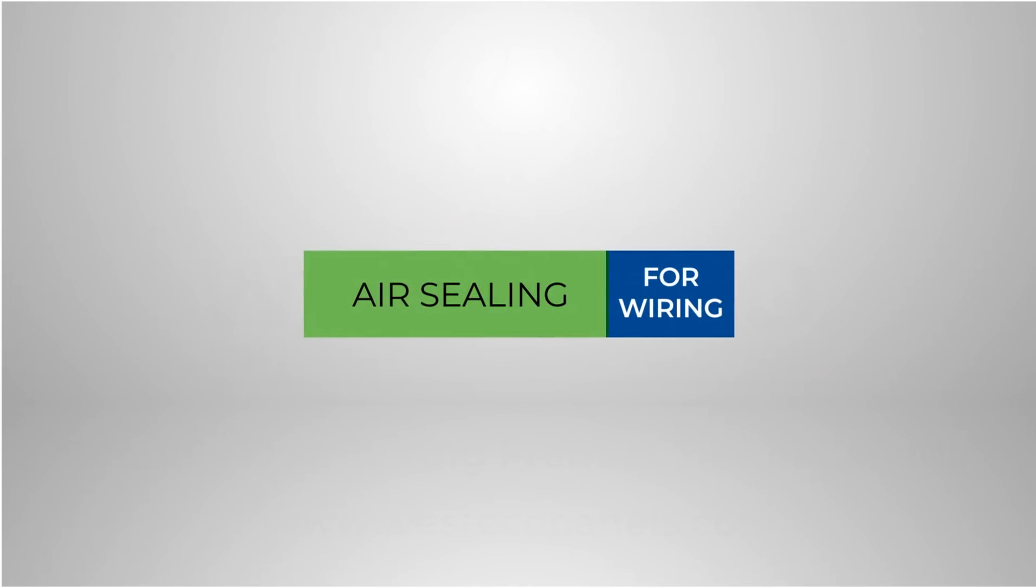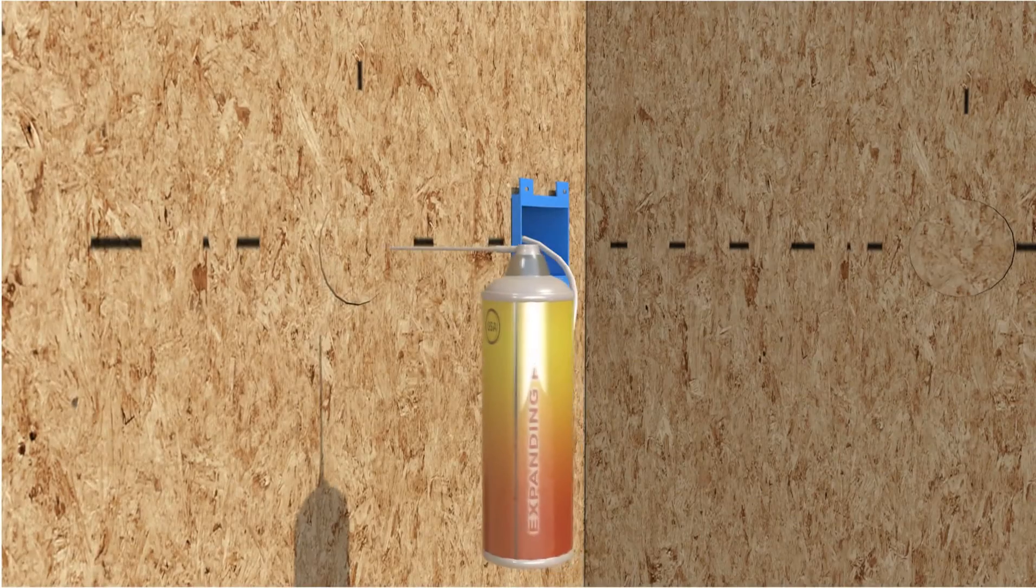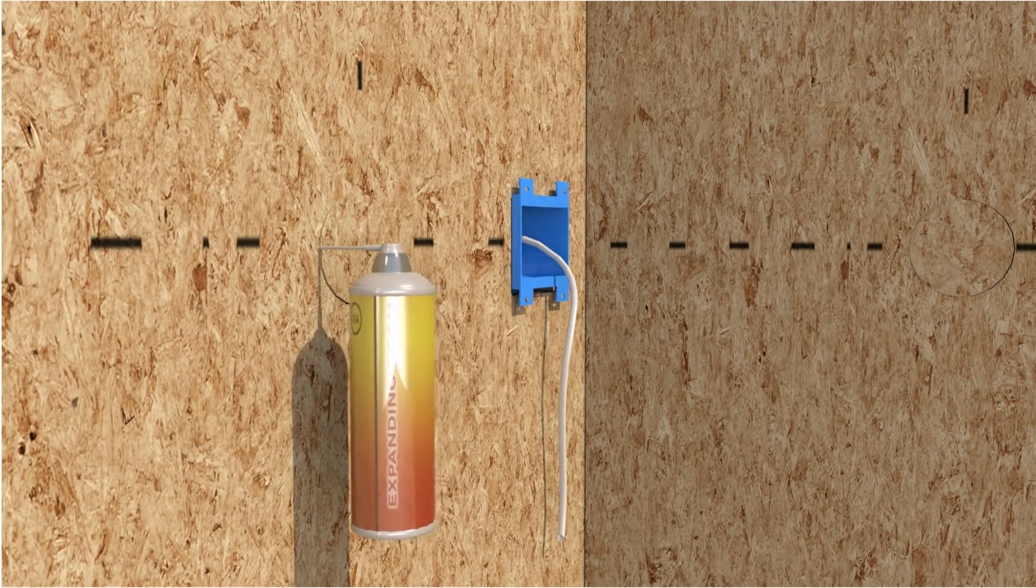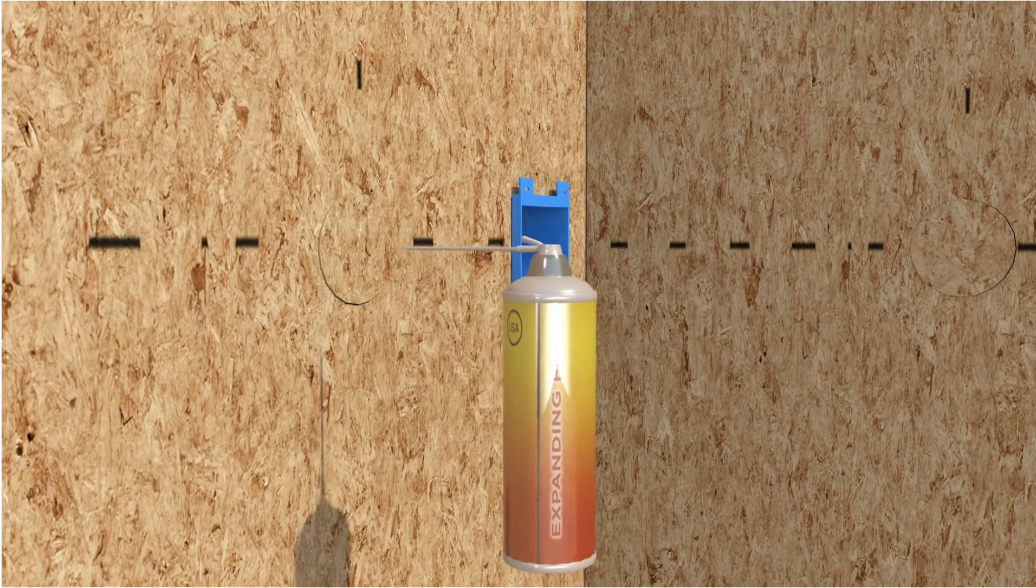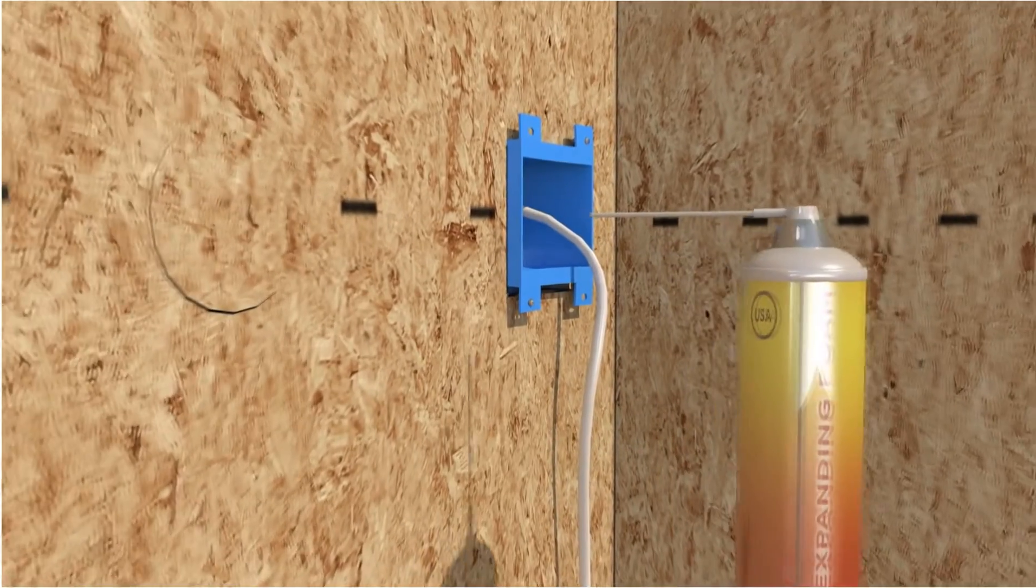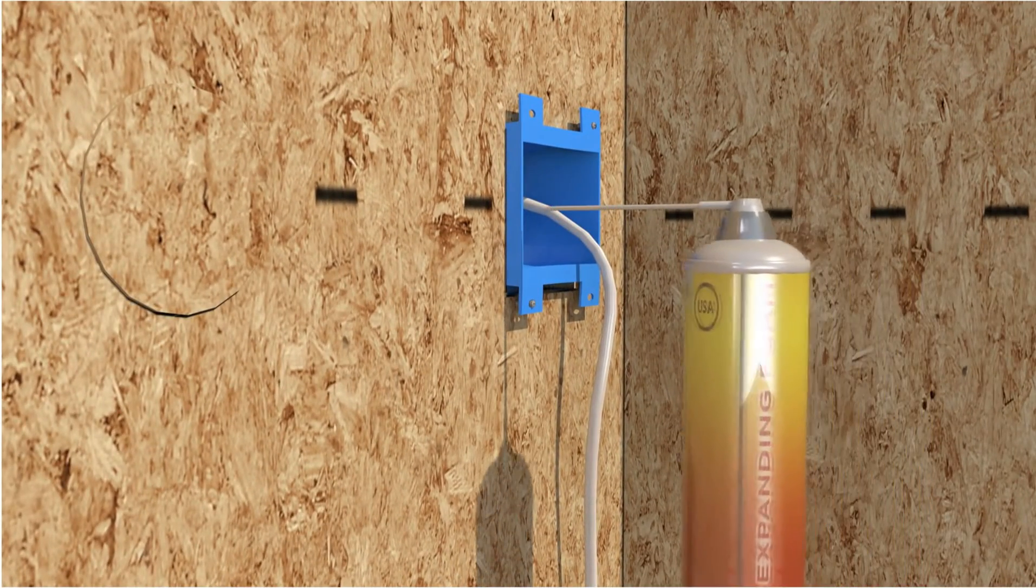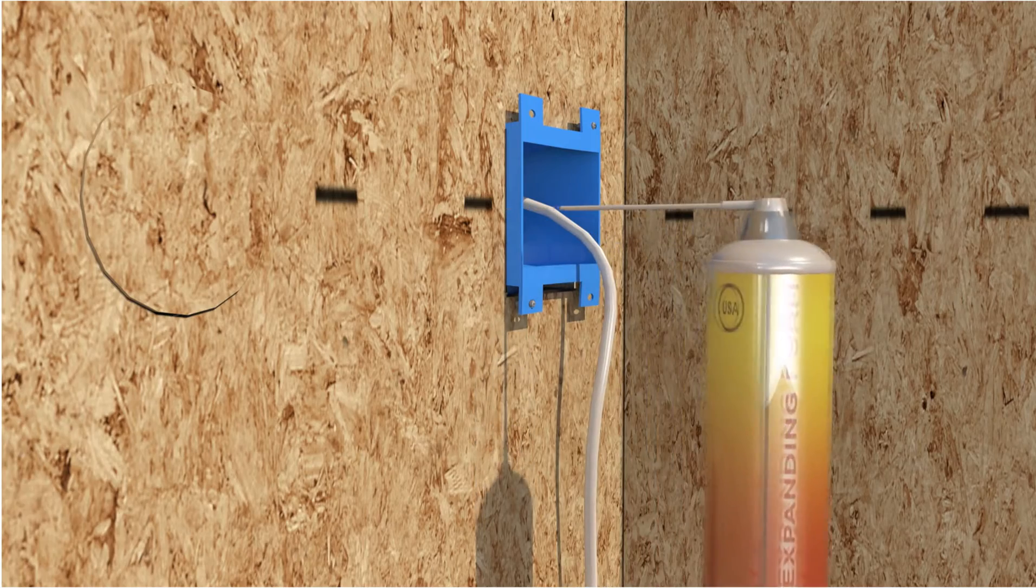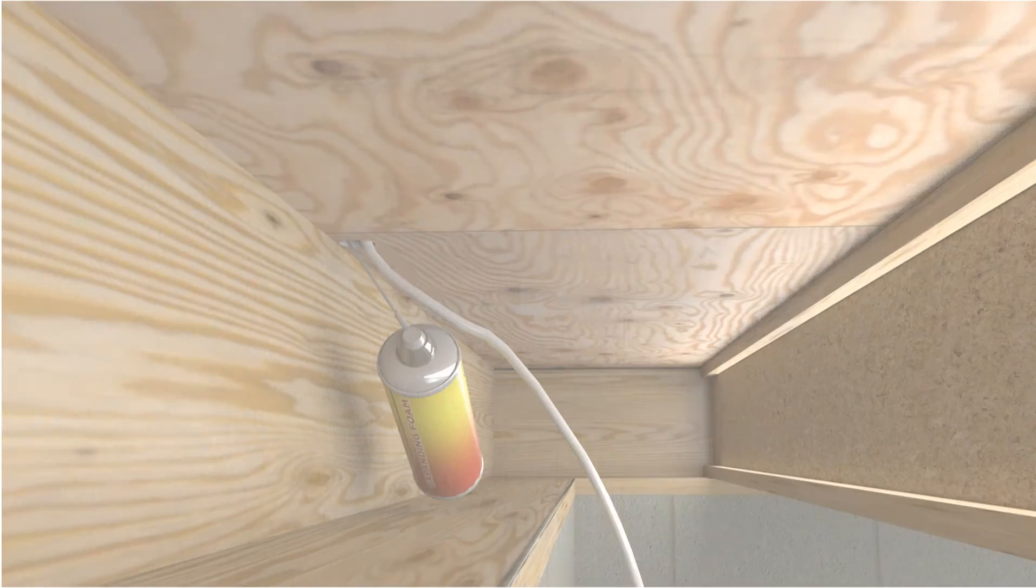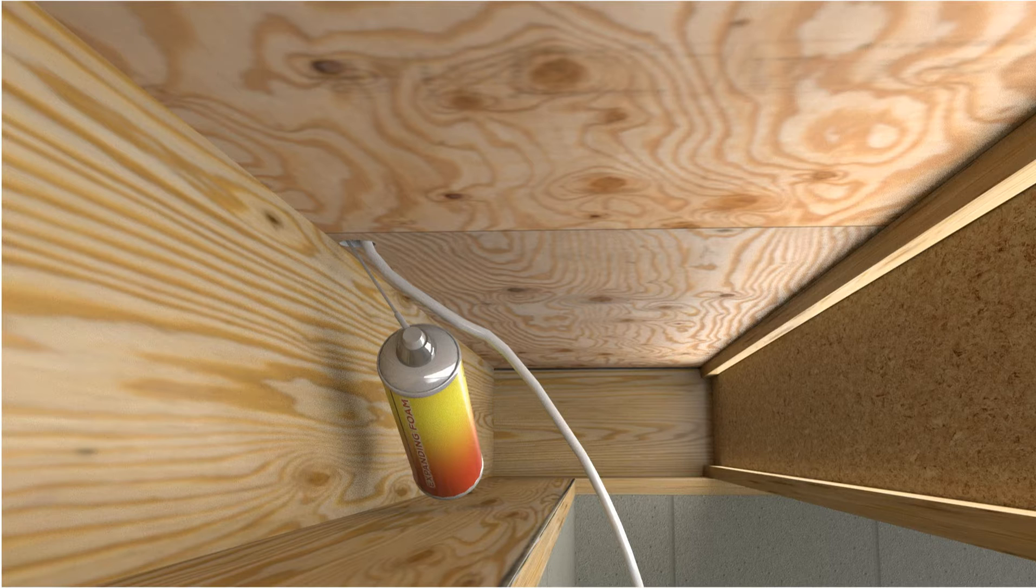Air sealing for wiring. After wiring is completed, use a low expanding foam to fully seal the electrical chase behind all boxes and any unused cutouts. Remember to foam seal all interior and exterior wall electrical boxes. All wire access holes used or unused must also be foam filled.